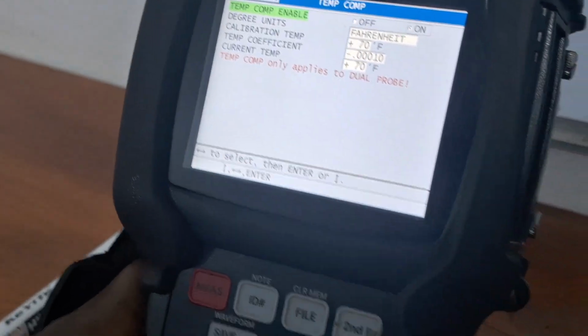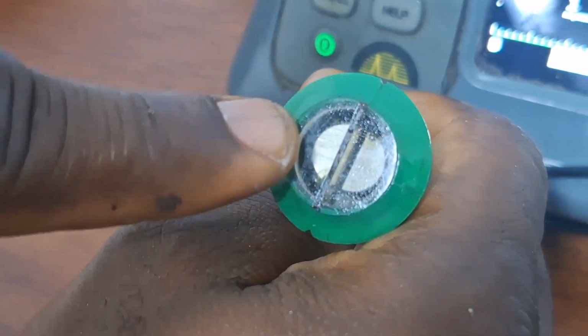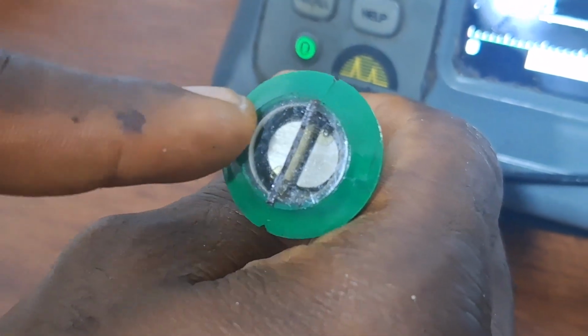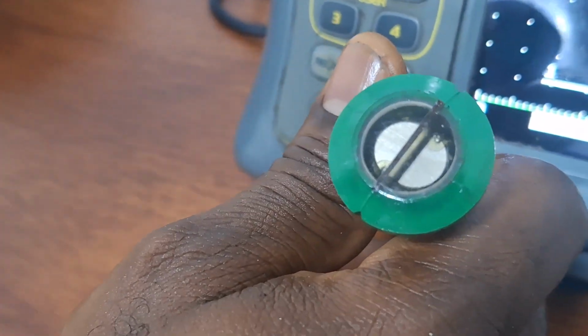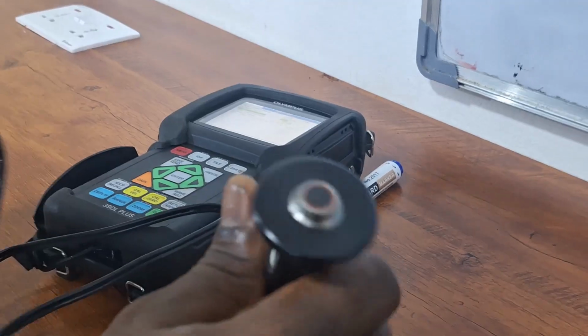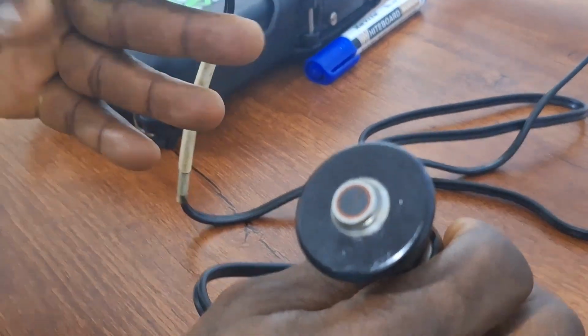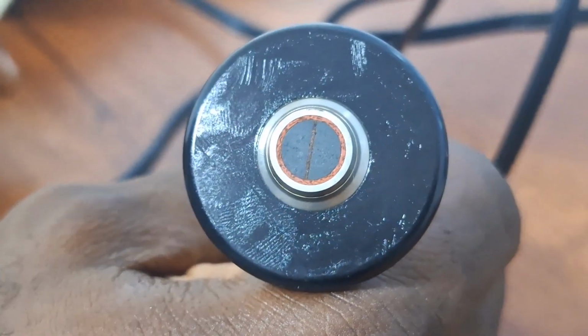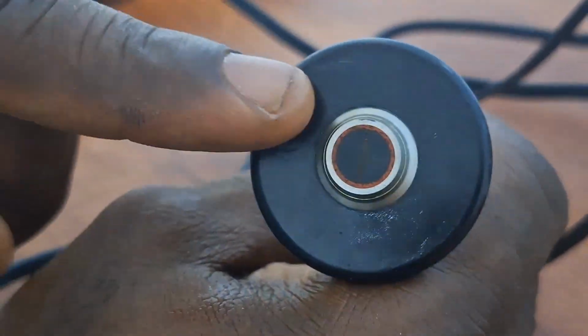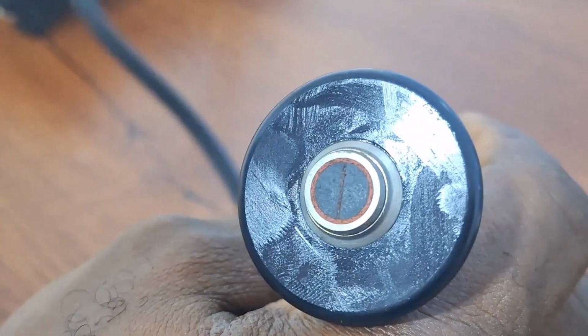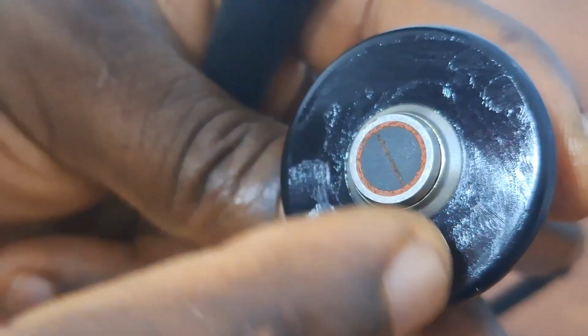Now, if you look at this probe I'm holding here, this is a dual probe. You can see the two elements inside separated by this partition. Which means this probe is suited for high temperature. This also is a double element probe which you can also use for that purpose. But if you have a single element, do not use it. How do you verify? You see the partition in between that separates the probe. So if you look at this, you have this partition.